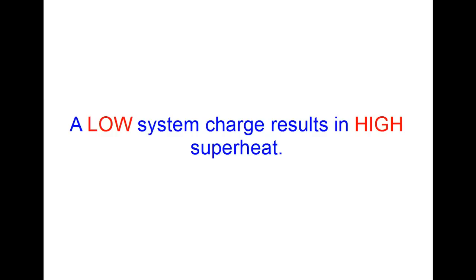Okay, so the thing to remember, a system that is low in charge results in high superheat and we'll take a look in our next video at a system that is overcharged and see what that does to the superheat. All right, any questions, message me in our learning management system or send me an email.